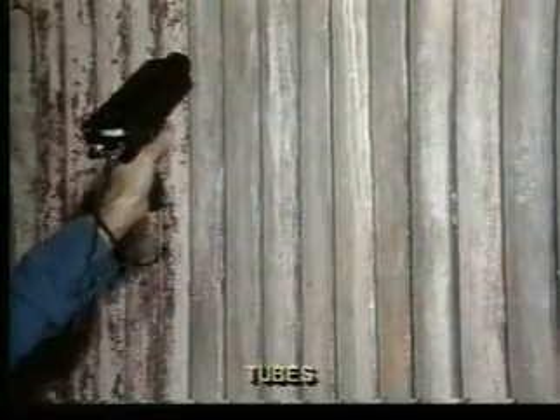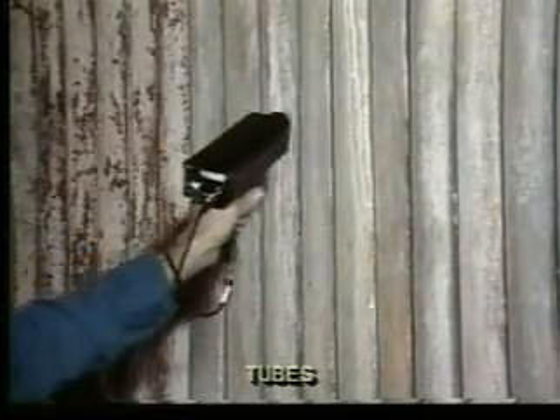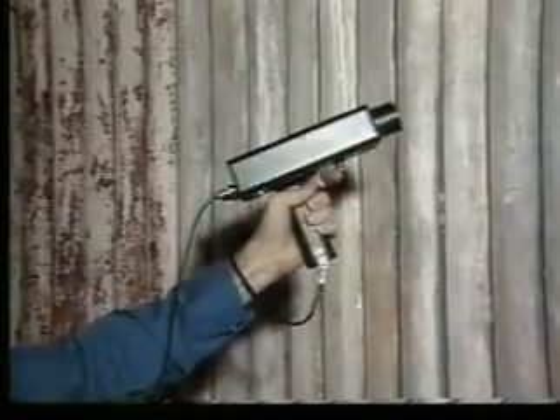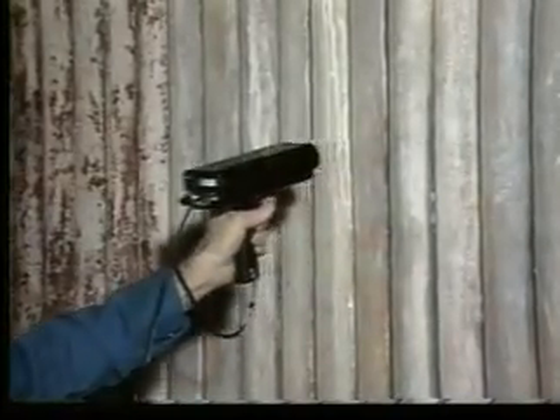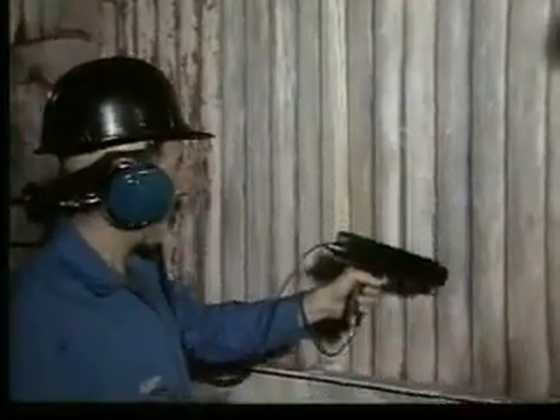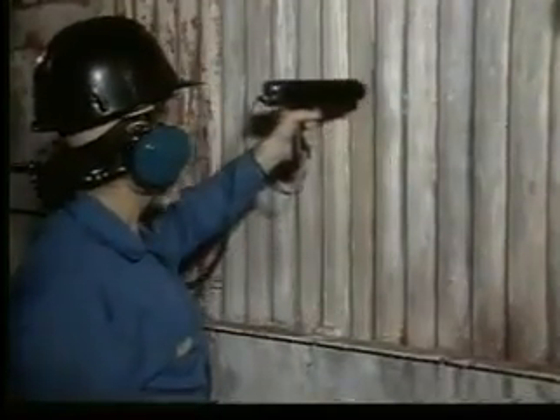When testing tubes with the system pressurized, use the scanning module. If there is steam in the tubes, it will be necessary to scan at a distance. Note the area with the loudest sounds. Adjust the sensitivity to pinpoint the leaking tube. Next, we'll discuss testing condensers.